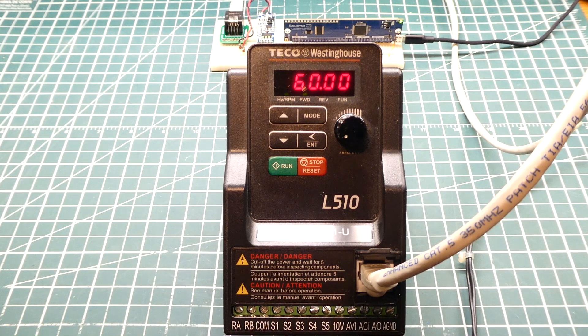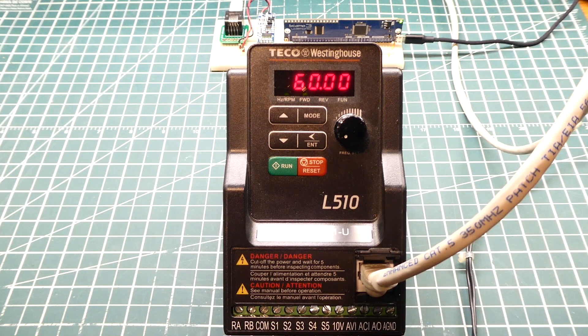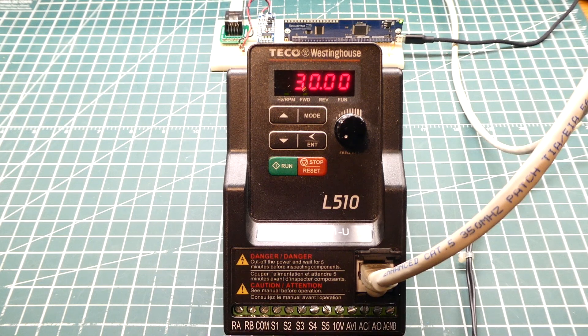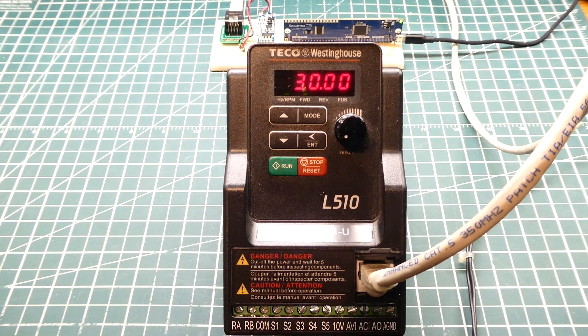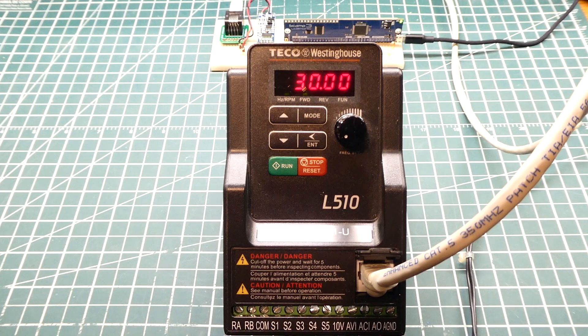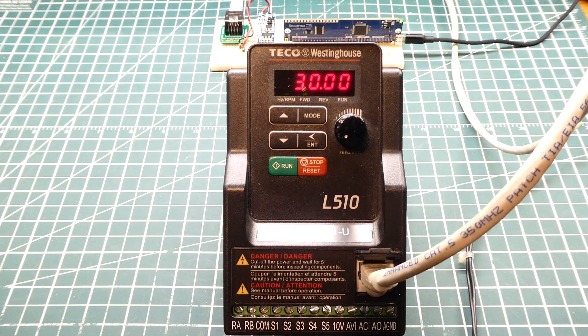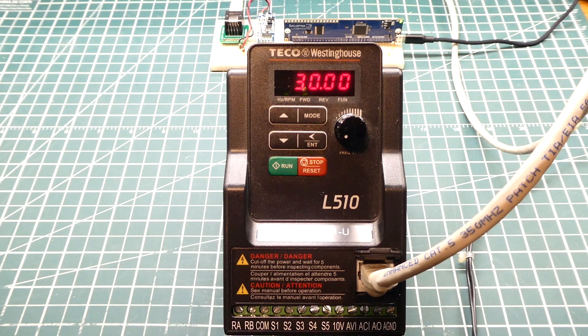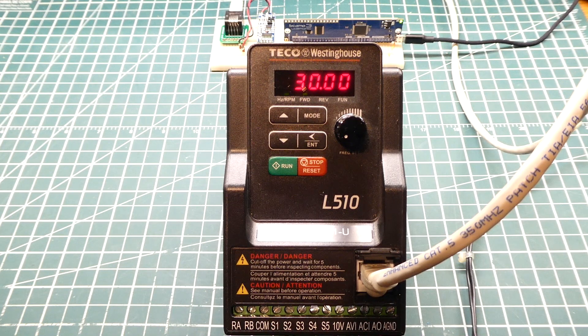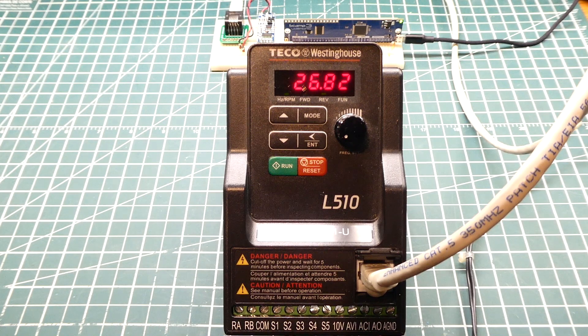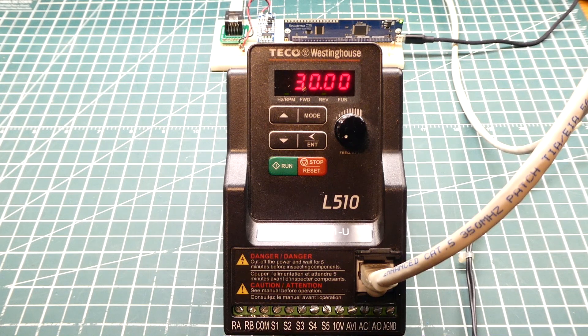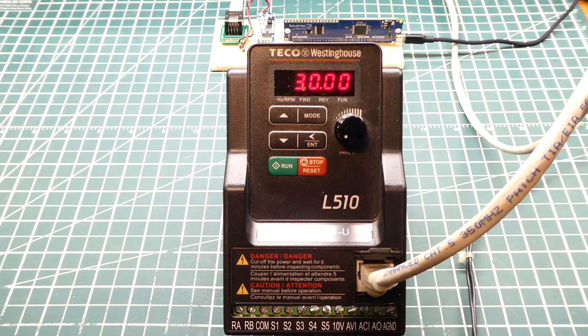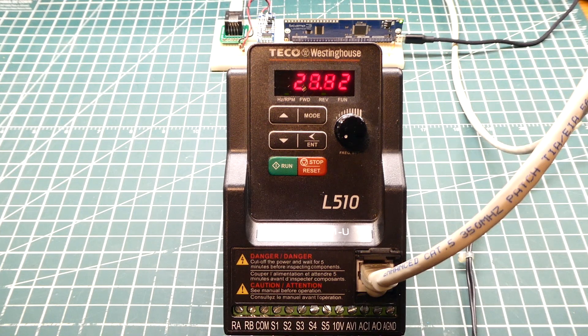I'll take it down to 30 hertz again. And I'll change direction, you can see it's in forward mode, I'll go reverse. Now if you're going in forward mode and you switch it to reverse, it's going to ramp it down to zero. And then it's going to switch directions and ramp it up, so you can see that happening. So I'll go reverse, it's ramping down, and it's ramping up, and it's in reverse mode. And if I hit zero hertz, it'll give me a stop.